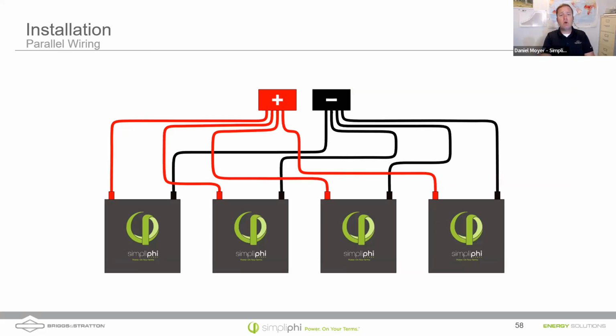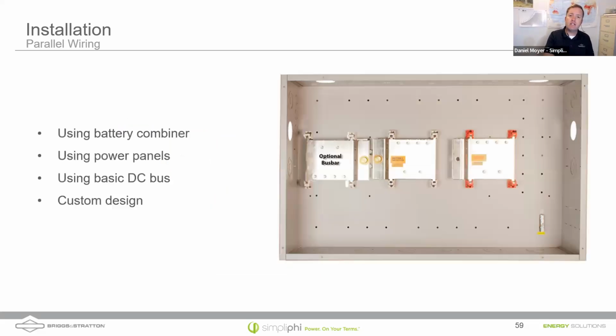We talked about this. We always want you to wire our batteries in parallel, never in series. And when you do wire them in parallel, in most situations, I'm going to want you to use conductors of the same gauge, of the same length, go into a common connection point, like a bus bar or a terminal block. That's going to ensure that each battery is working just as hard as the next.